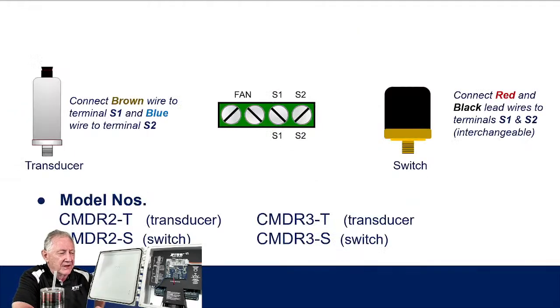I think I've got a picture of these. There you go. All right, so on the left-hand side is a typical pressure transducer. When this drive ships out, it's going to ship with a 100 pound pressure transducer. That's standard. If you look at the model numbers down below, it's going to indicate which one is going to ship with a transducer, which one is going to ship with a switch. All right, so there's 4 model numbers for the 2 drives.